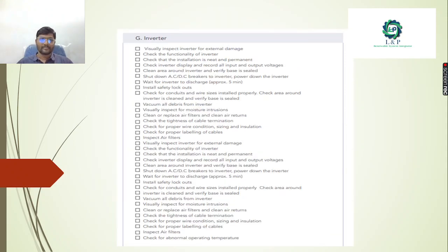Next, on the inverter side, make sure the display is okay. Is it showing any sort of errors or warning symbols? If there is a warning, try to resolve it. Whenever you do the maintenance, always install the safety lockouts there. Make sure your AC and DC breakers are proper. If it is switched on, check whether the production is okay or not, and check for any abnormality owing to temperatures.